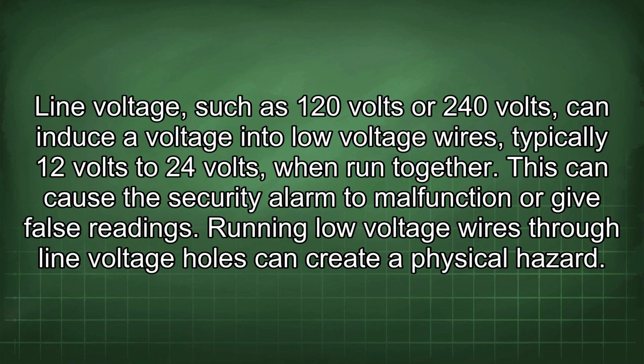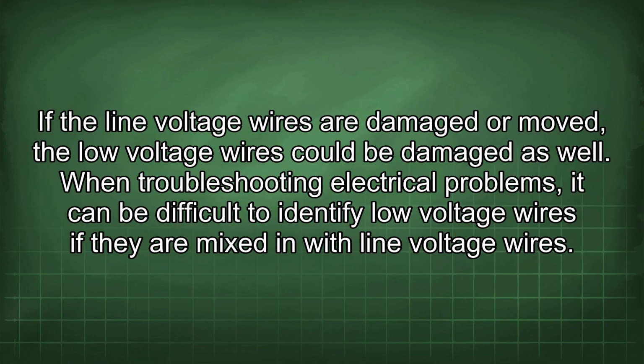Line voltage, such as 120 volts or 240 volts, can induce a voltage into low voltage wires, typically 12 volts to 24 volts, when run together. This can cause the security alarm to malfunction or give false readings. Running low voltage wires through line voltage holes can create a physical hazard. If the line voltage wires are damaged or moved, the low voltage wires could be damaged as well.